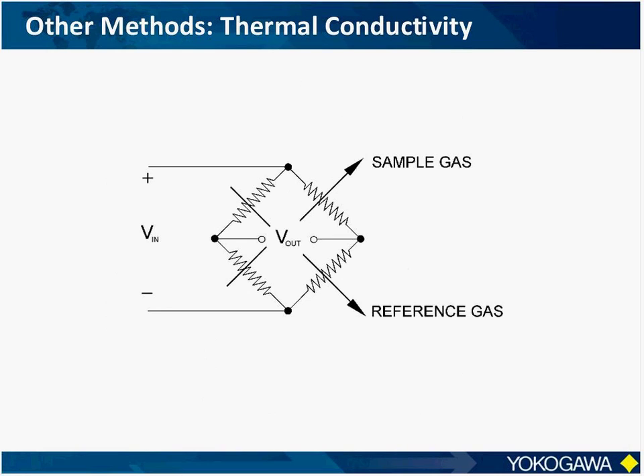Thermal conductivity is another method employed to measure percent concentration in binary gas streams. Each gas has the ability to conduct heat at a specific rate, so this is known as the thermal conductivity of the gas. In thermal conductivity analyzers, heated metal filaments or thermistors are exposed to reference and sample gases. The amount of heat carried away by the gases changes the temperature of the filaments, which also changes their resistance. And since the filaments are arranged in a Wheatstone bridge, the resistance can be converted to an electrical current. And the magnitude of this current is going to be dependent on the thermal conductivity of the two gases. And that way, the concentration of the sample gas is calculated based on the thermal conductivity value.